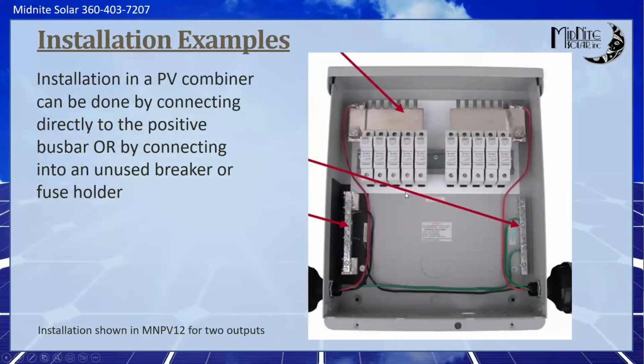So here's a better picture of what I was talking about. Sue got me a better picture for this one for sure. So this bus bar has these holes in it where you can crimp the ring terminal on the SPD and land it right on the bus bar. Now, that being said, let's say you were only using 4 strings on each side instead of 5. You could put it under a fuse holder and put a 30-amp fuse in there. That would be just as acceptable as well.